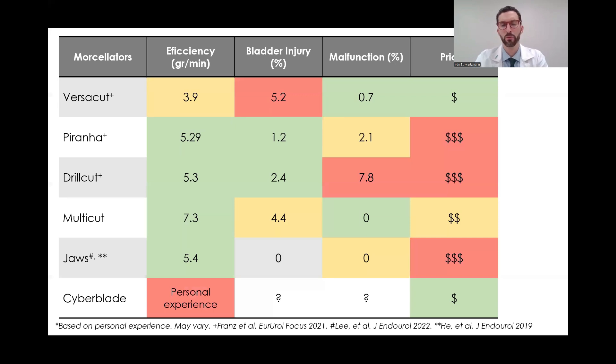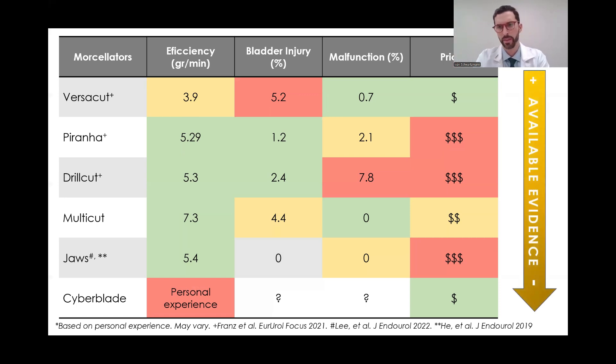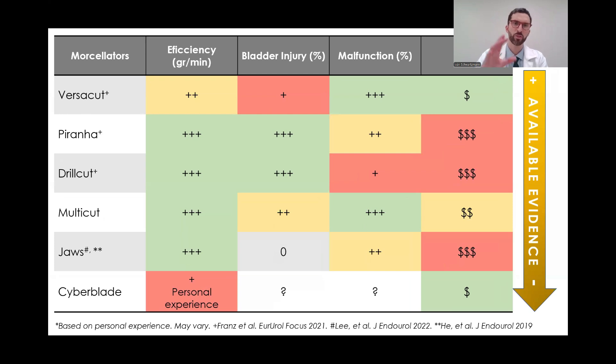Putting all the data into the summary table, there is a huge variation in available evidence. The Versacut and Piranha have a lot of evidence; the rest have very little. Converting exact numbers to categories: probably the slowest morselators are the Versacut and the Cyberblade, while all others have similar efficiencies — with the Piranha a little bit better in our experience. Regarding bladder wall injury rate, the Versacut is probably the worst. Regarding device malfunction, with available evidence, the Drillcut is probably the worst.